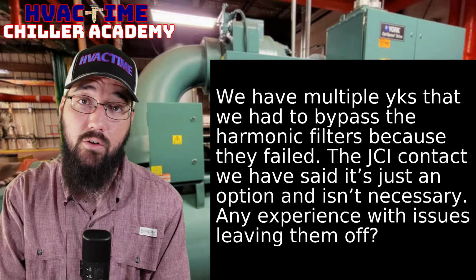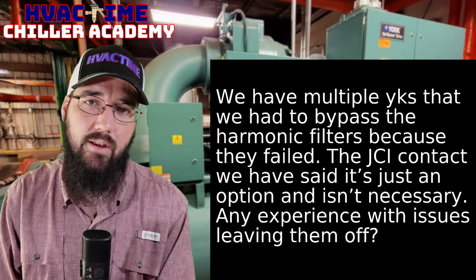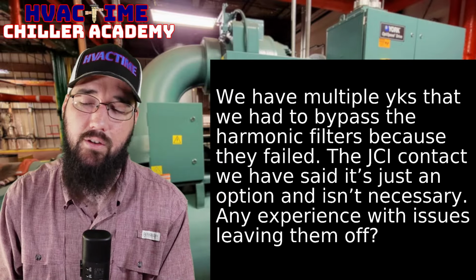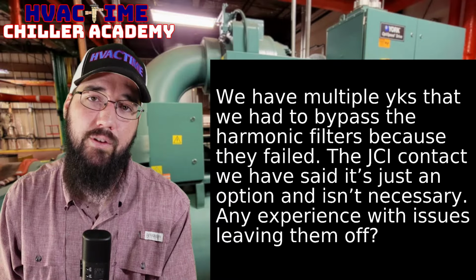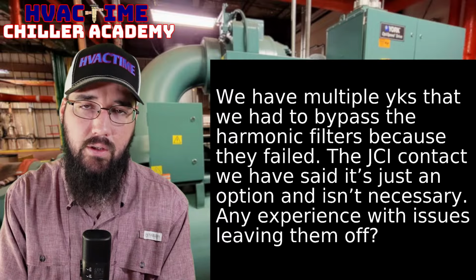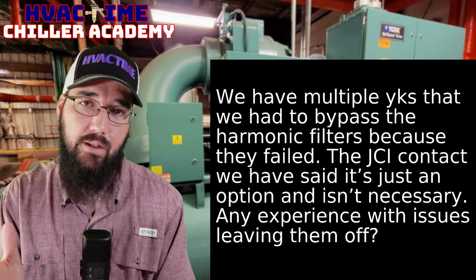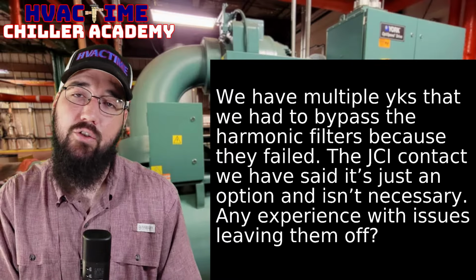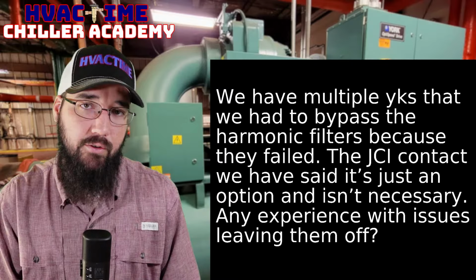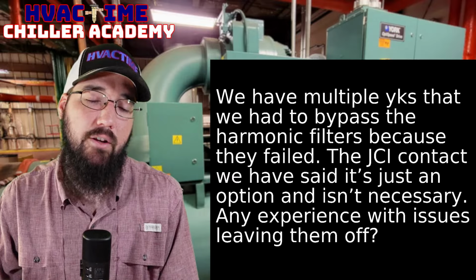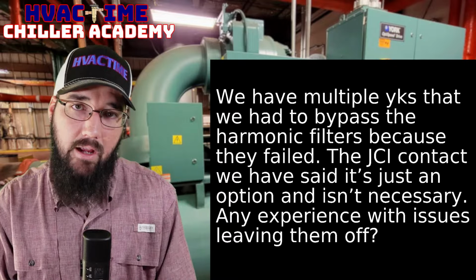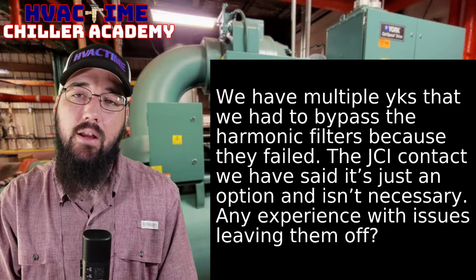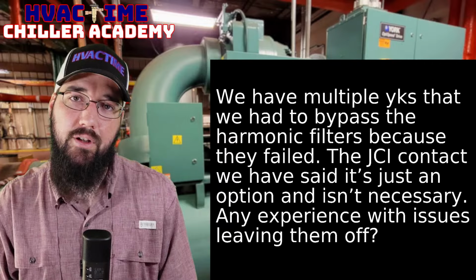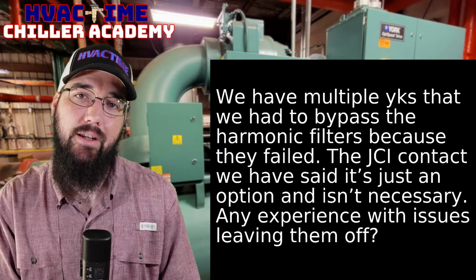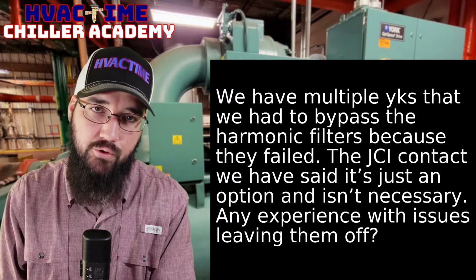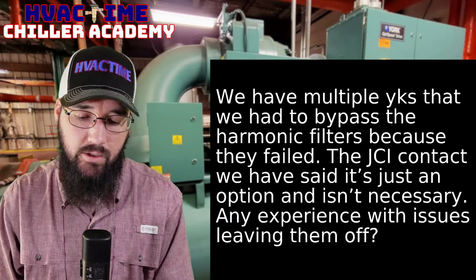So that's something to be aware of. And this is also true for small drives, right? So based out of Austin, Texas, we have a really dirty power grid. It's horrendous. And it is routine to constantly have to replace drives, just regular ones like Danfoss VLTs or an ABB 550, 580, just standard drives on pumps or air handlers, things like that. Those are routine replacements because they're getting fed dirty power, and while they've gotten better with time, they have better internal filtering than they used to have, it's still not enough to really clean up what they're being given. So it leads to routine failures on those drives. Same thing is true for these larger drives we're using on these centrifugals and such.